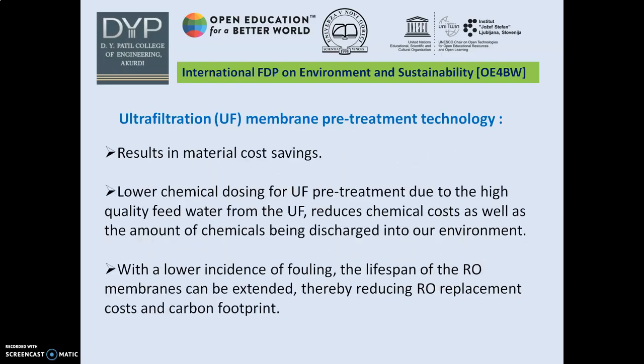It results in material cost savings. Lower chemical dosing for UF pre-treatment, due to the high quality feed water from the UF, reduces chemical costs as well as the amount of chemicals being discharged into our environment. With a lower incidence of fouling, the lifespan of the RO membranes can be extended, thereby reducing RO replacement costs and carbon footprint.